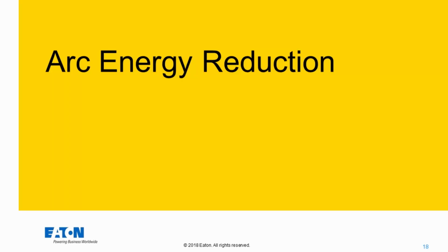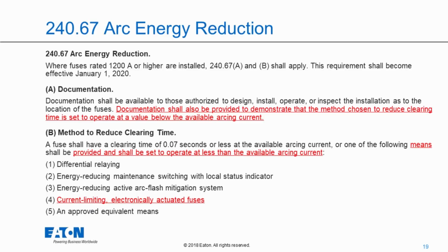So the next one is arc energy reduction, and this really is an interesting discussion. Arc energy reduction has been in the NEC. It's been a concern for the NEC, primarily for larger ampacity circuit breakers. And what we saw in the 2017 edition of the NEC was a requirement that addressed large ampacity fuses. And the guideline they decided to take for that was where fuses rated 1200 amps or higher are installed. So this does not apply to lower ampacity fuses.